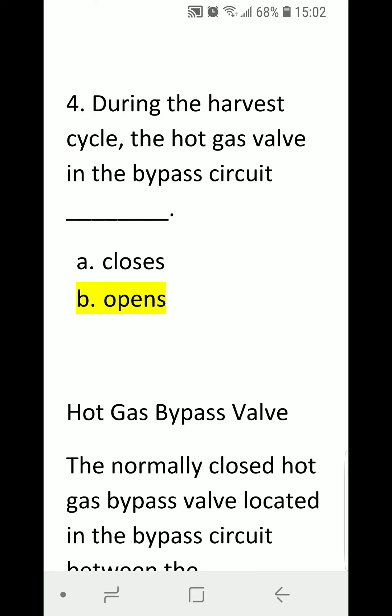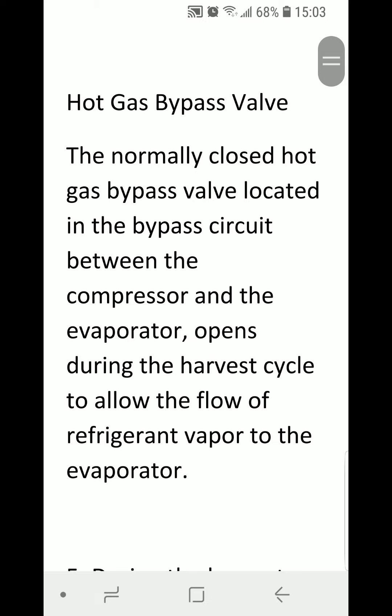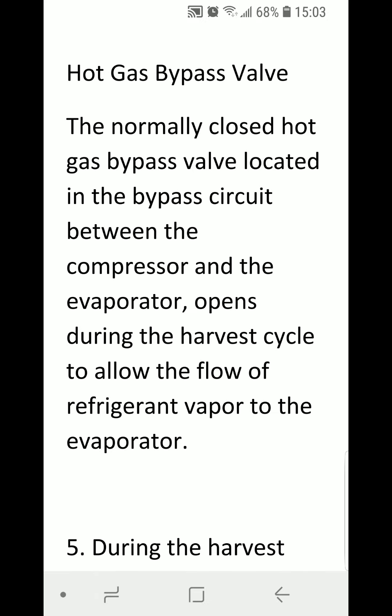Number four: during the harvest cycle, the hot gas valve in the bypass circuit — A) closes or B) opens. The normally closed hot gas bypass valve, located in the bypass circuit between the compressor and the evaporator, opens during the harvest cycle to allow the flow of refrigerant vapor to the evaporator.